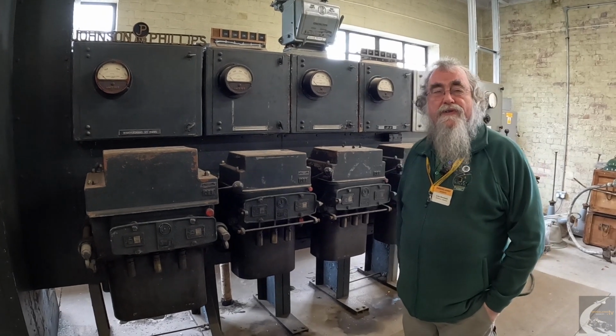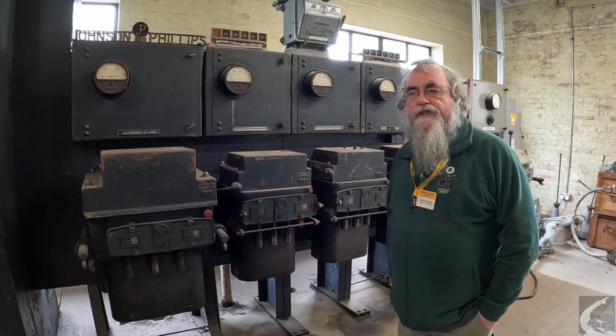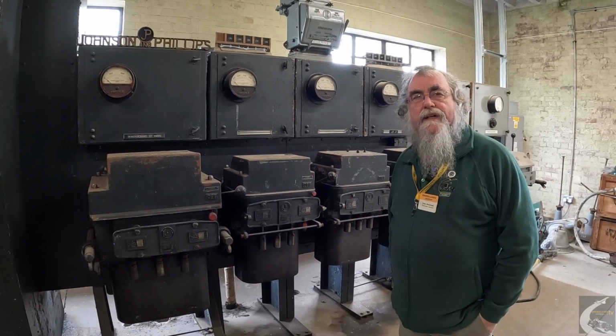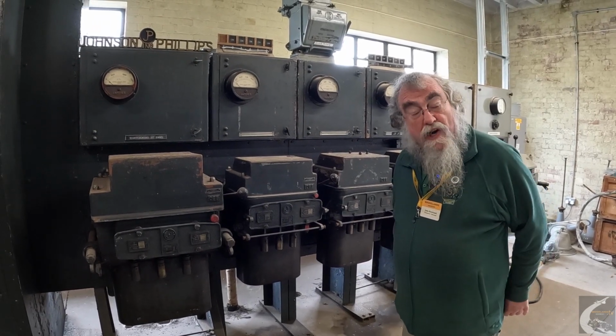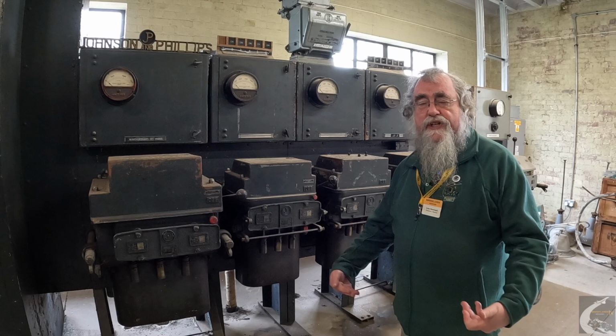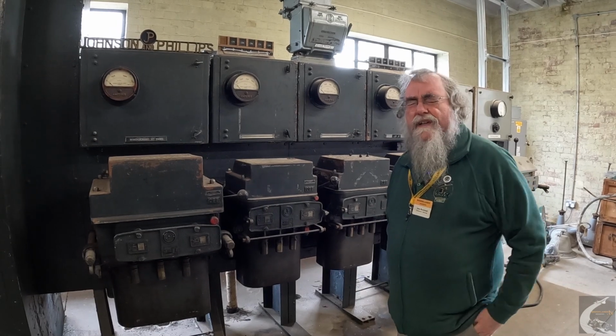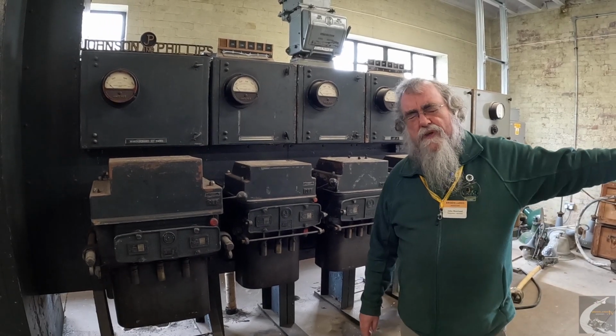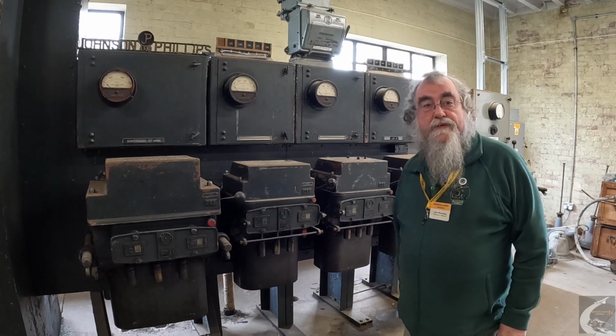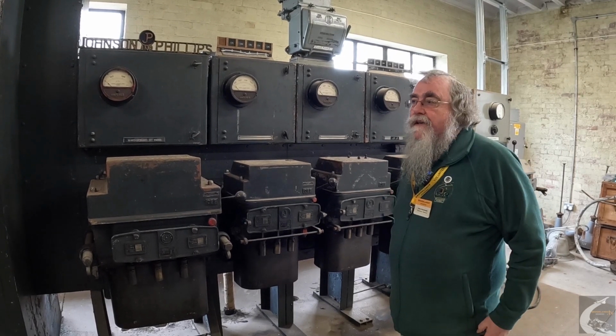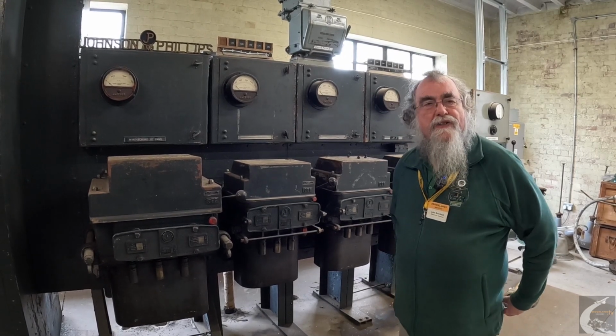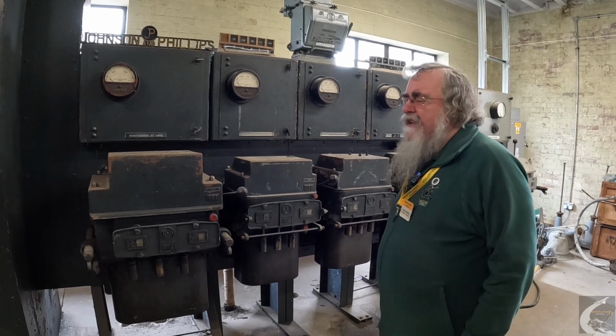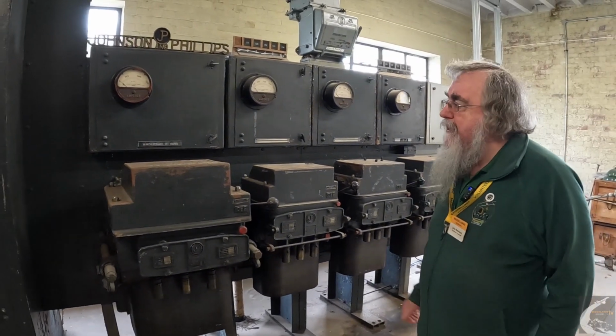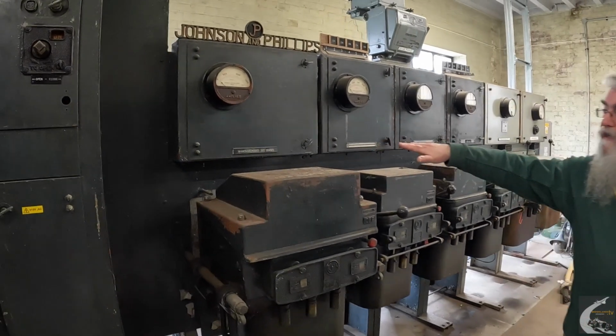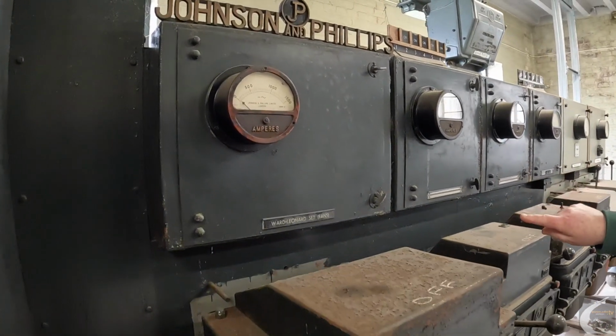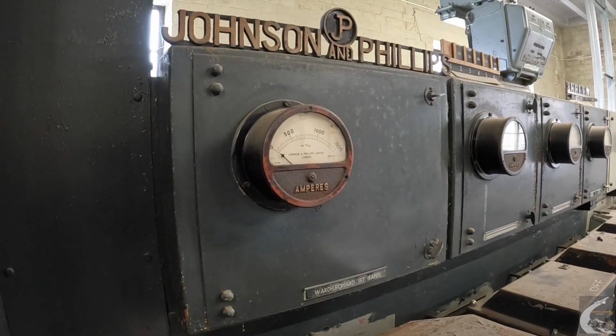So you basically took a DC motor and changed the field coils in terms of the rating, the current through them, which would change the speed of the motor. The motor speed is controlled from the control room we've seen in another video, which you may like to check out. But to generate the DC, you have what's known here as the Ward-Leonard set, and that's why it says fans - it fed the fans.